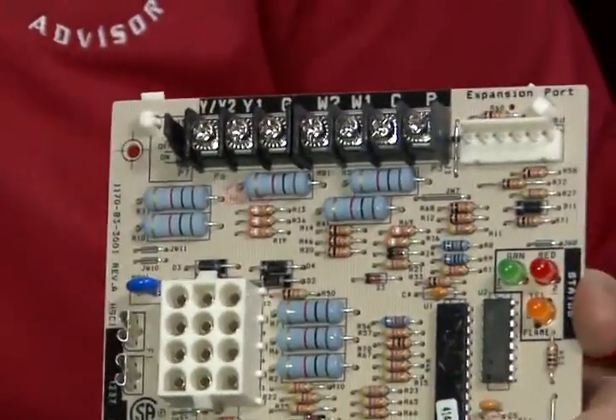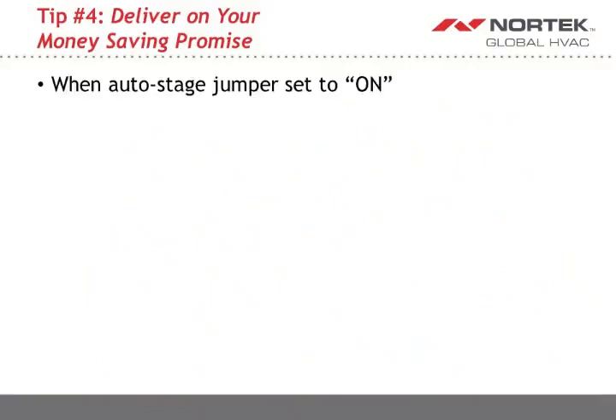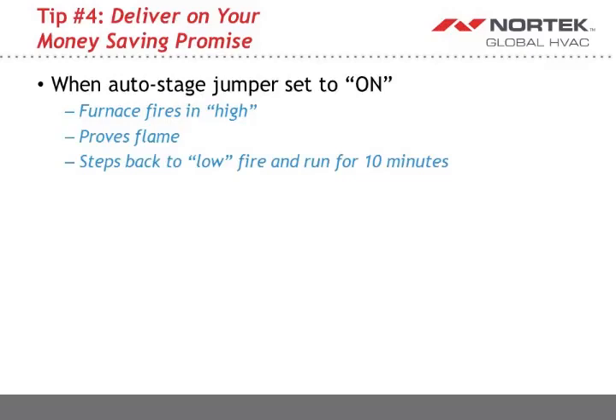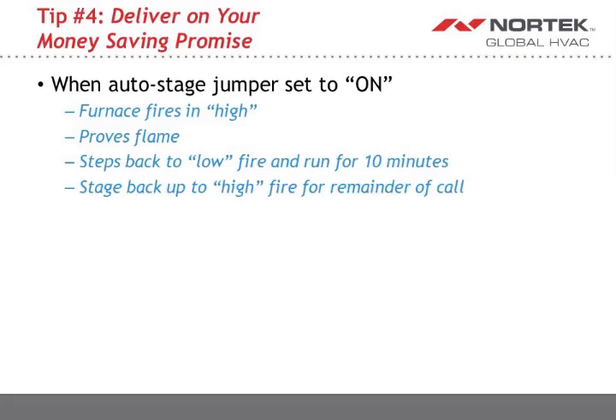Even without landing anything on the W2 terminal, if you just land on W1, if you place that auto stage feature so the jumper shunt lines up with on, then the furnace will fire in high, it will prove flame, it will step back to low fire, it will run for 10 minutes, and then after 10 minutes has elapsed, it will stage itself back up to high fire and then run through the remainder of that call in high fire. No more confusing thermostat setups or anything like that for an owner that might possibly be wanting to shy away from multiple stage equipment because of the increased technology factor, if you will.